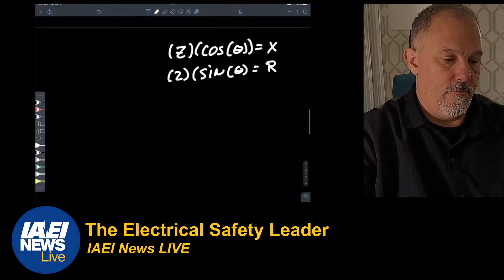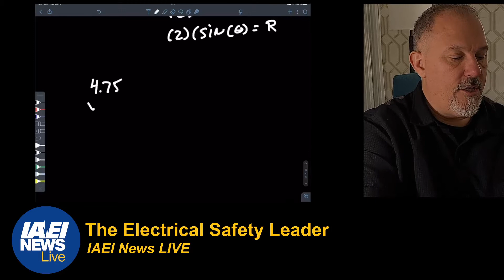So you could break down those values. Let's go back while that's loading up. Let's say my X to R ratio is... say I told you that you have an impedance of 4.75 and an X to R ratio of 3. I'm just making numbers up. What does that mean? It means my Z is 4.75 and my tangent of theta is equal to 3.